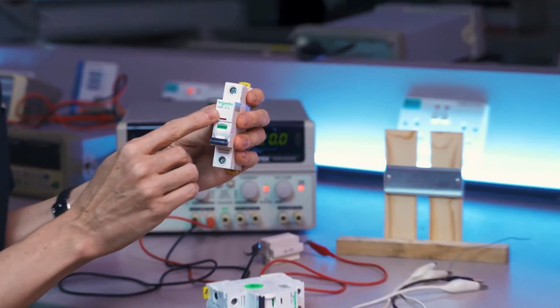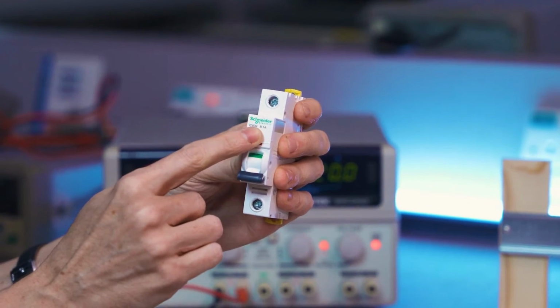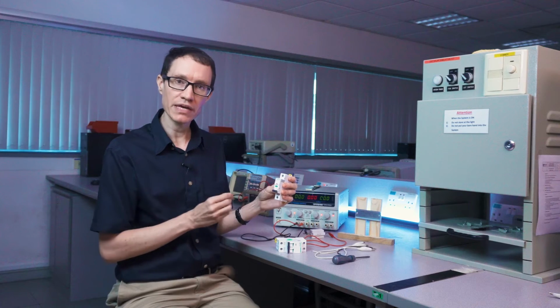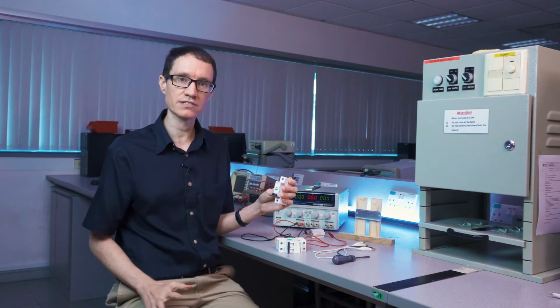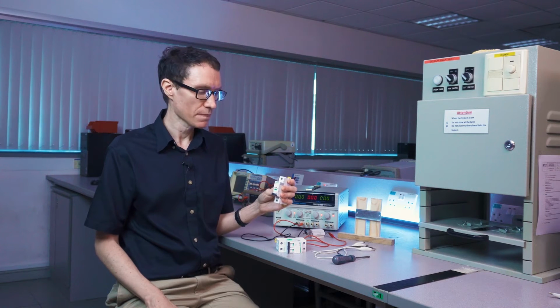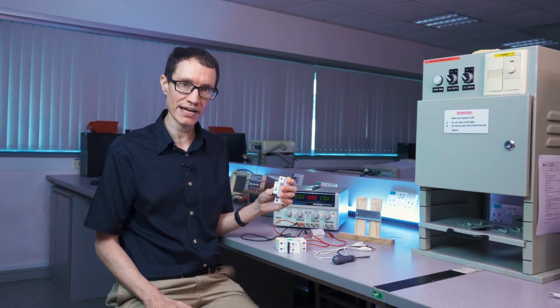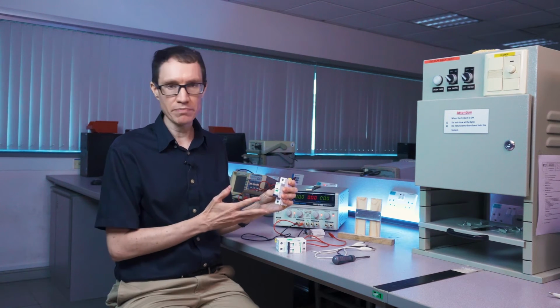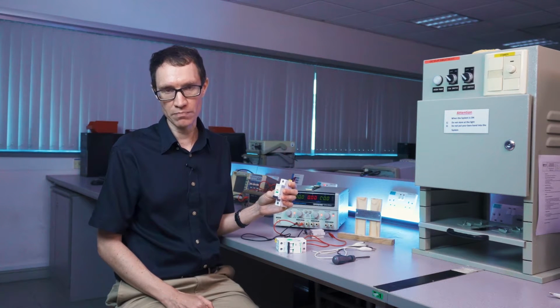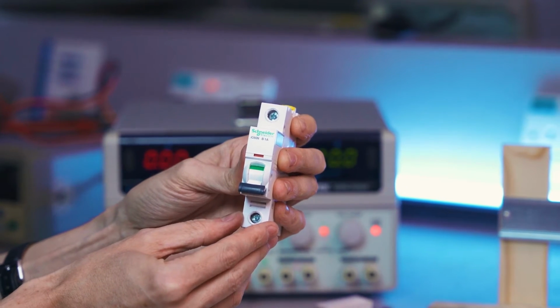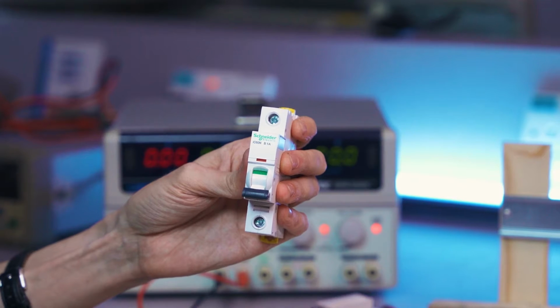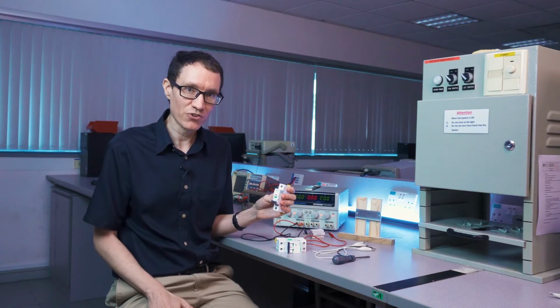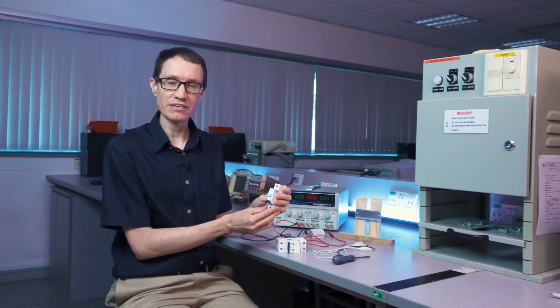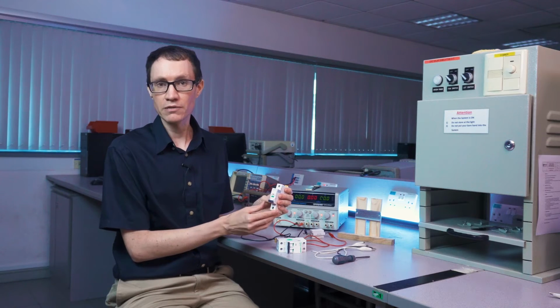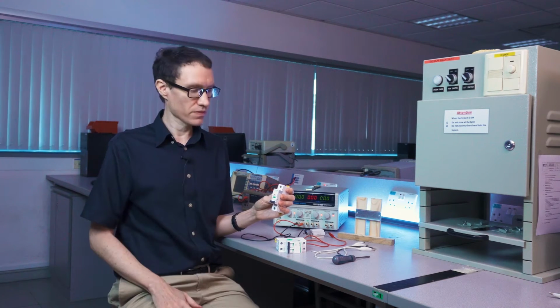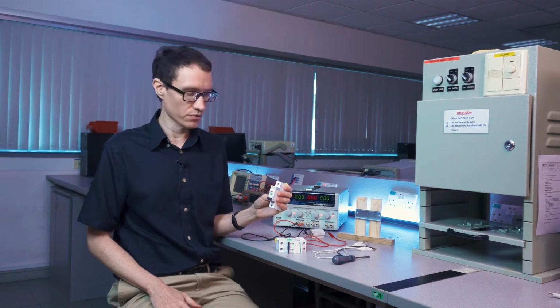On the front part of this circuit breaker here, it's labeled B 1 ampere. B refers to the trip curve, and I'll say something more about that in a moment. And 1 ampere refers to the maximum allowable current that you can pass through the circuit breaker without it tripping. If I flow exactly 1 ampere, or say 1.1 amperes of current through this breaker, that doesn't mean it's going to trip instantly. The amount of time it takes a circuit breaker to trip depends on how much more than the rated current you try to send through the circuit breaker.